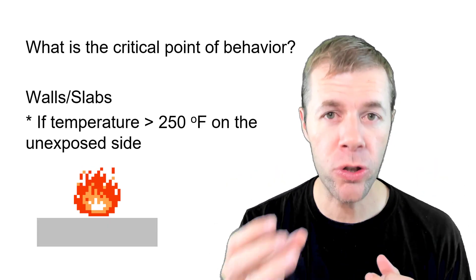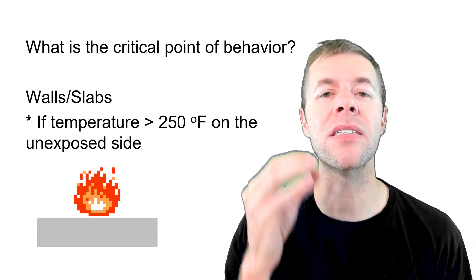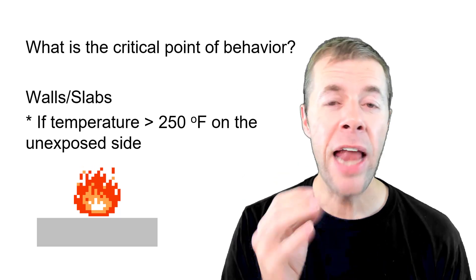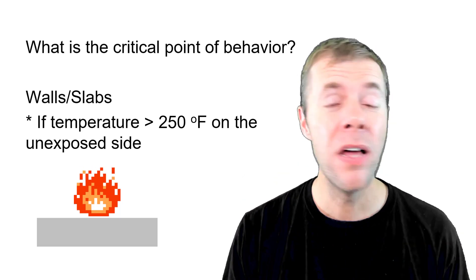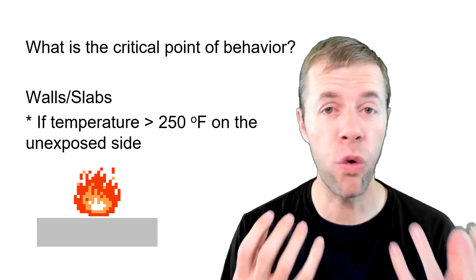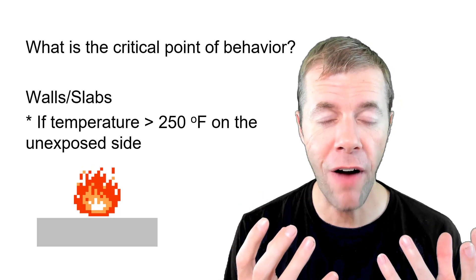So what they want is the temperature on the other side of the member to be less than 250 degrees Fahrenheit. If it takes two hours to get there, then that's a two hour fire rating. If it takes four hours, that's a four hour fire rating.